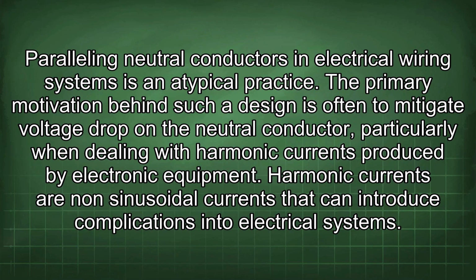Paralleling neutral conductors in electrical wiring systems is an atypical practice. The primary motivation behind such a design is often to mitigate voltage drop on the neutral conductor, particularly when dealing with harmonic currents produced by electronic equipment. Harmonic currents are non-sinusoidal currents that can introduce complications into electrical systems.